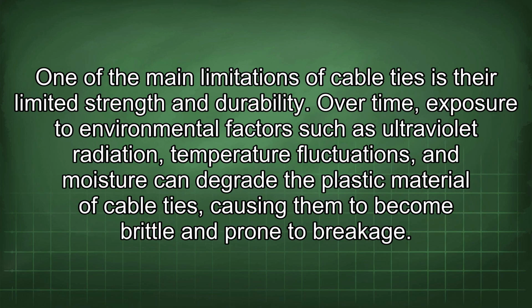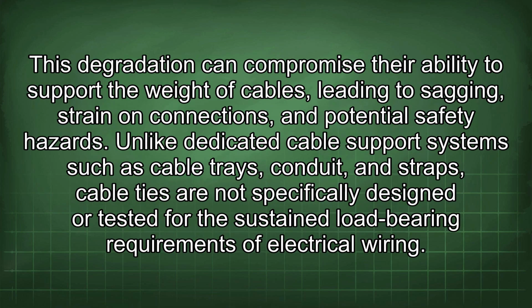One of the main limitations of cable ties is their limited strength and durability. Over time, exposure to environmental factors such as ultraviolet radiation, temperature fluctuations, and moisture can degrade the plastic material of cable ties, causing them to become brittle and prone to breakage. This degradation can compromise their ability to support the weight of cables, leading to sagging, strain on connections, and potential safety hazards.